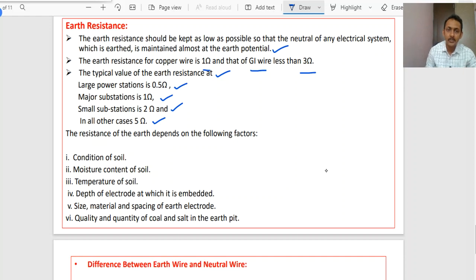Right? Now, as we discussed earlier, the resistance of the earth is going to depend upon the following factors: condition of the soil, moisture content of the soil, temperature of the soil, depth of the electrode at which it is embedded or inserted, right, and the size, material and spacing of the earth electrode. We have discussed the length, breadth and height dimensions of the copper or galvanized iron materials, their size, material and spacing of the earth electrode, and also the quality and quantity of coal and salt in the earth pit, which grade of coal you are using, right, and the quality and quantity of the rock salt we are using.